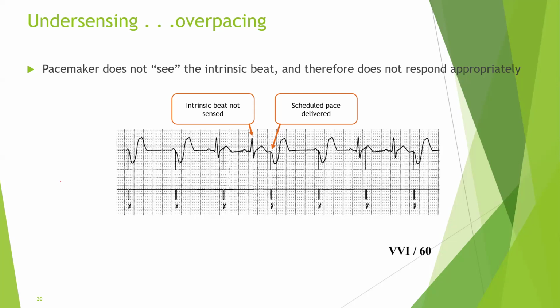Yes, doctor. We have to reduce the sensitivity, right? Here you have to reduce the sensitivity, or you have to change the polarity of the sensitivity. For example, you test your lead, you find the bipolar R wave is 2. So you must now test the unipolar R wave, see how big the unipolar R wave is. And the unipolar R wave, for example, is 4 or 5. So you program your sensitivity now unipolar rather than bipolar, because your bipolar sensitivity and R wave is very small, and it will result in undersensing and overpacing.